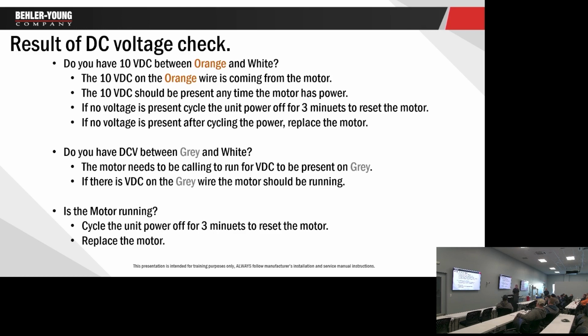Do I have voltage on gray? If I do, the motor should be running. If I don't, the motor's bad. I mean, if I have volts DC and the motor's not running, the motor's bad. If I don't have volts DC, then I'm going to go back and look at the gas control board. Do I have the output from that? Like I said, if the motor's not running, kill the power for 3 minutes. And yes, be patient. We need to give it 3 full minutes for the capacitor to discharge.